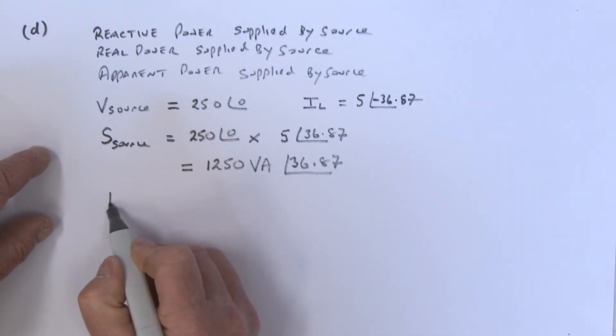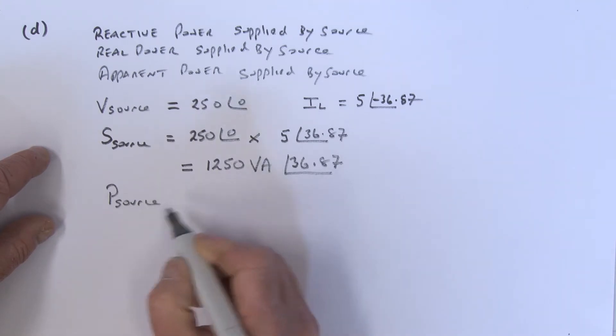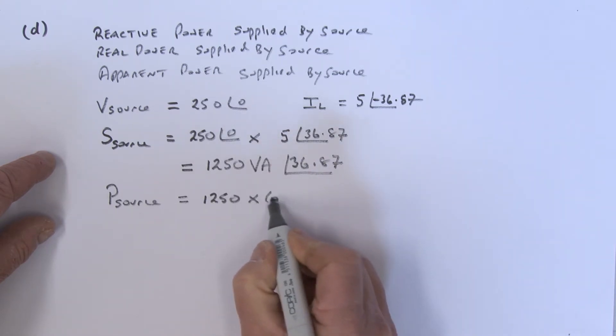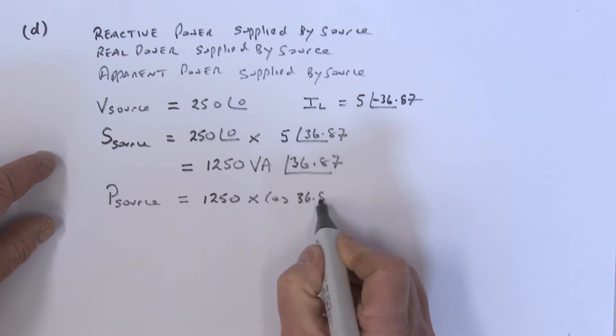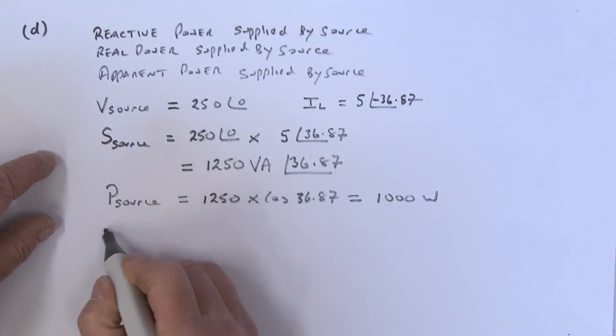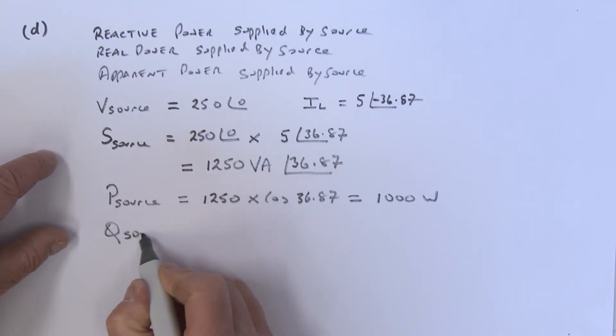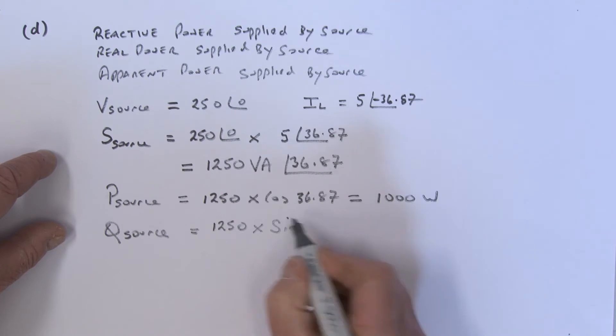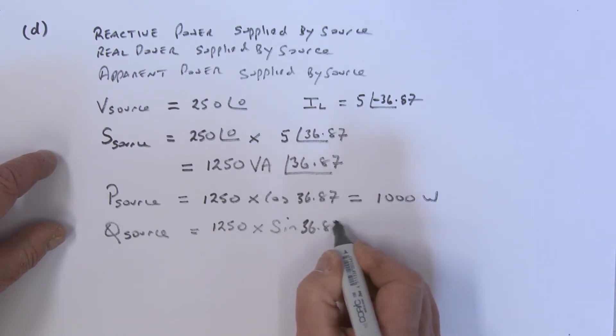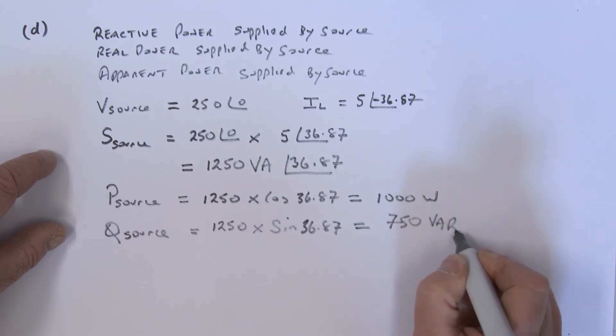Knowing the angle and power factor, the real power supplied by the source is 1250 multiplied by cosine of 36.87 degrees, which equals 1000 watts. The reactive power supplied by the source is 1250 multiplied by sine of 36.87 degrees, which equals 750 volt-amps reactive.